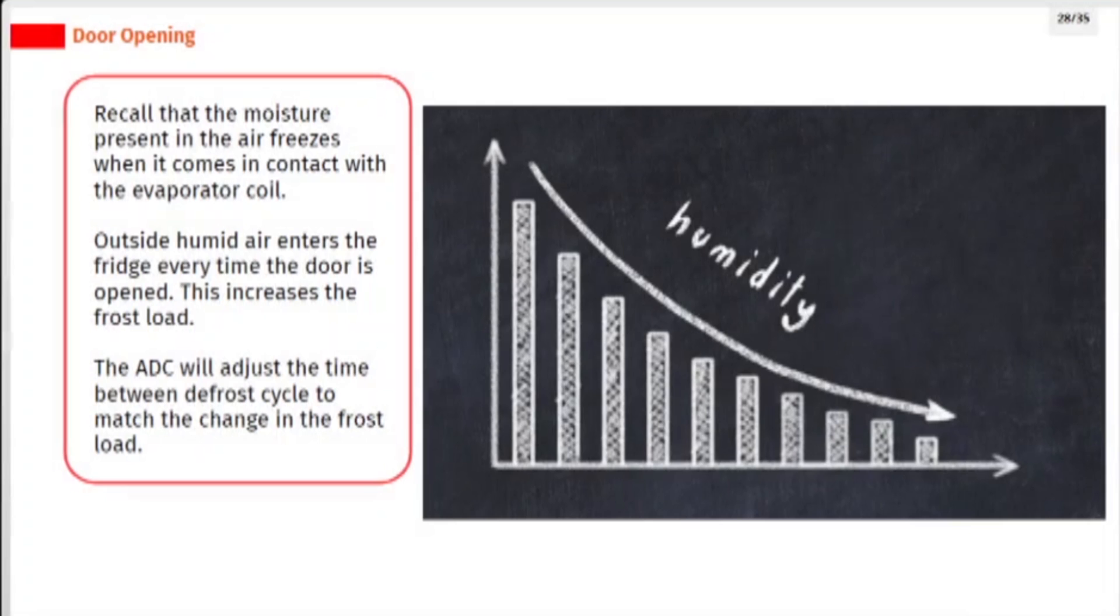Recall that the moisture present in the air freezes when it comes in contact with the evaporator coil. Outside humid air enters the fridge every time the door is opened. This increases the frost load. The ADC will adjust the time between defrost cycle to match the change in the frost load.